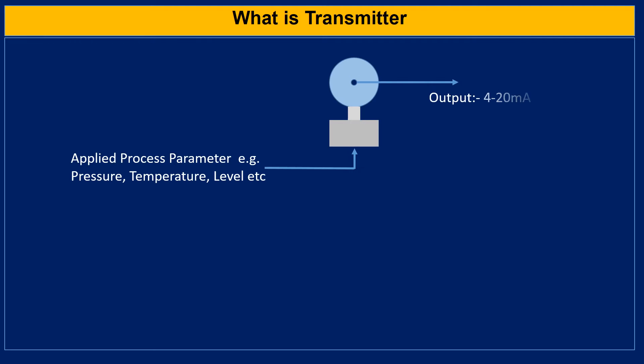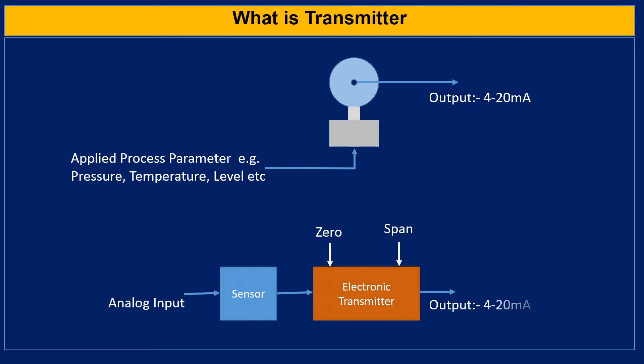A process transmitter is a device that senses the process parameter and converts it into a standard instrumentation signal. This signal is proportional to the value of the variable being measured. A transmitter often combines a sensor and a transmitter unit. The sensor senses the process variable and the transmitter converts it to a standard signal like 4 to 20 mA, 1 to 10 V, or 3 to 15 PSI.